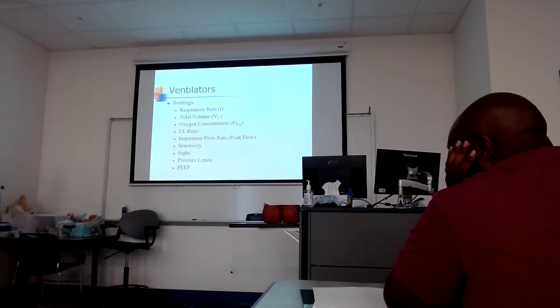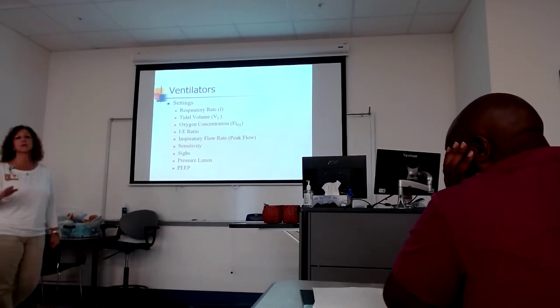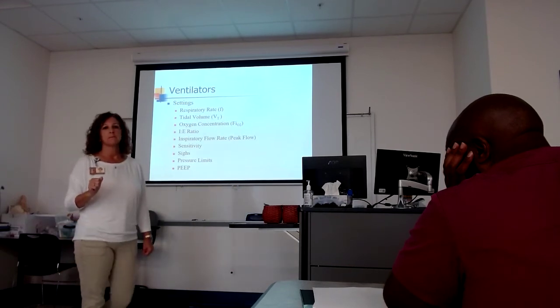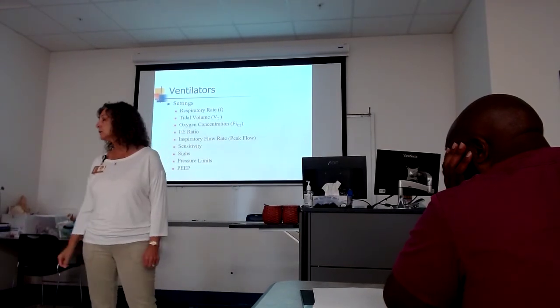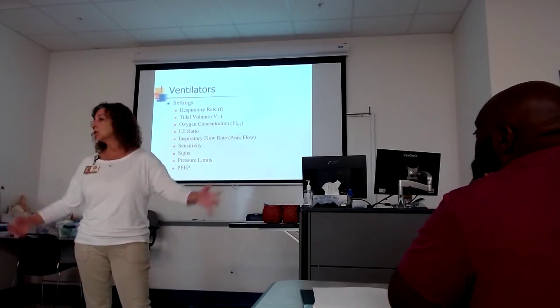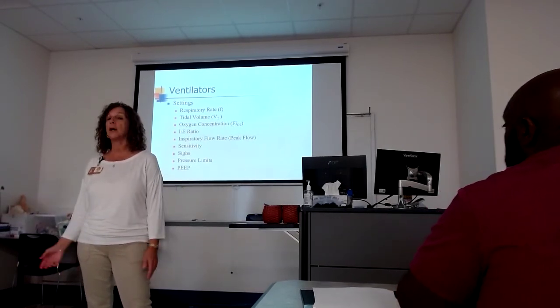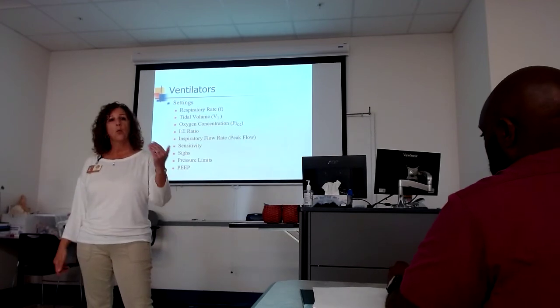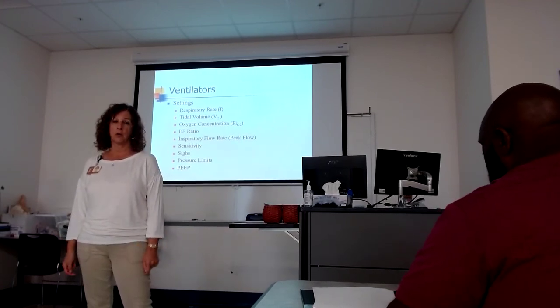Okay? So, Pierce, I know you have prepared. Low pressure alarm means what? First start with that. What does that mean? It's not meeting enough resistance. It's not meeting what it anticipated on resistance. It's like, okay, dude, I can do this all day long. This is easy peasy. I don't know what's going on, but I'm meeting very little resistance, not what I expected to meet. What are some potential causes of a low pressure alarm?